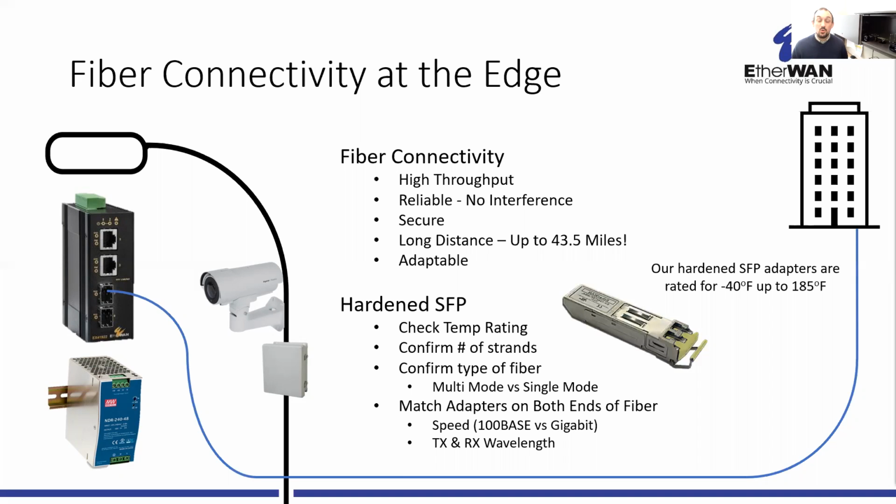You can't take the same one that you're used to using in your IT closet and throw it in your hardened switch in your NEMA enclosure out at the edge, because it's going to have a much lower point of failure temperature-wise compared to the rest of the solution, and you're only as good as that weakest link.